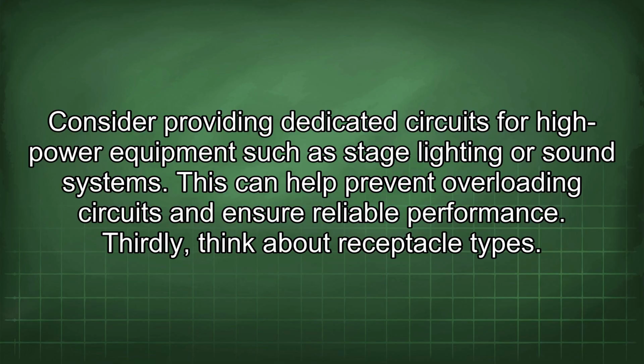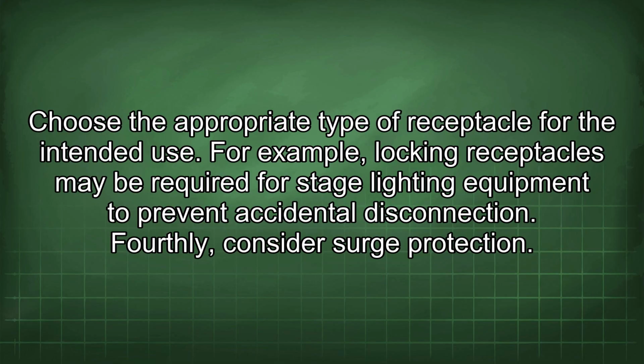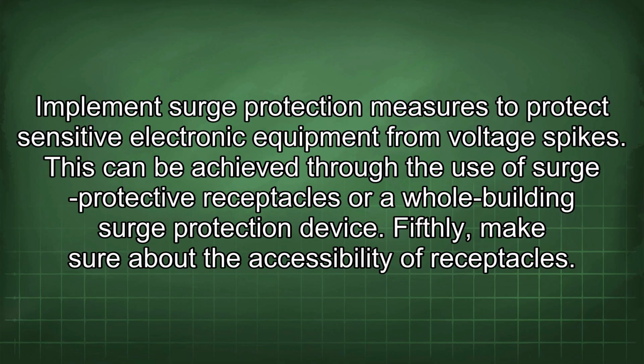Thirdly, think about receptacle types. Choose the appropriate type of receptacle for the intended use. For example, locking receptacles may be required for stage lighting equipment to prevent accidental disconnection. Fourthly, consider surge protection. Implement surge protection measures to protect sensitive electronic equipment from voltage spikes. This can be achieved through the use of surge protective receptacles or a whole building surge protection device.